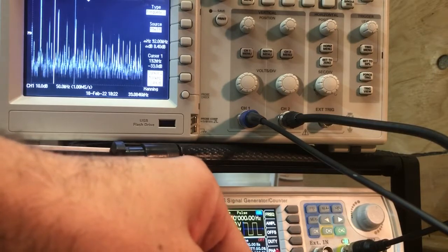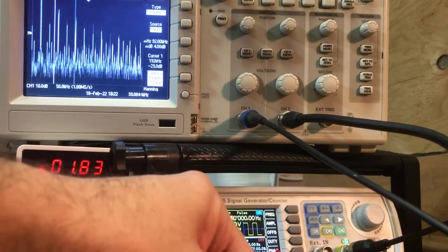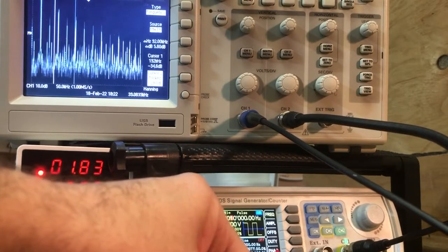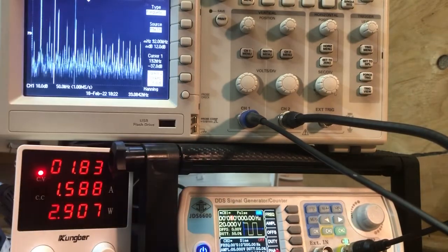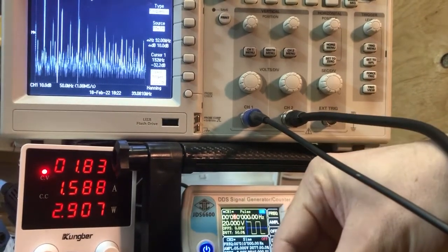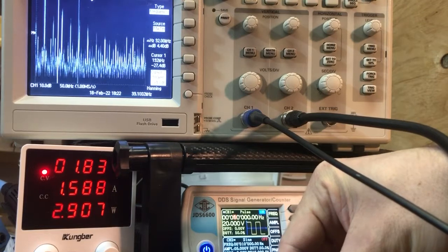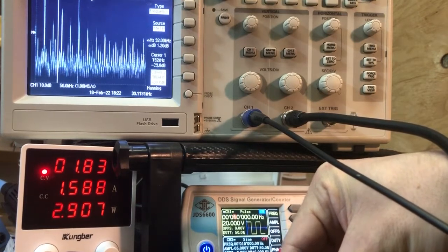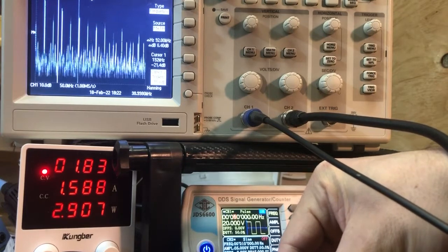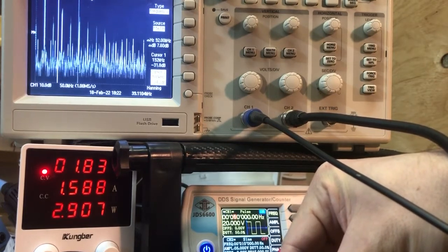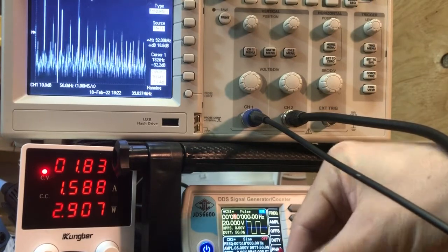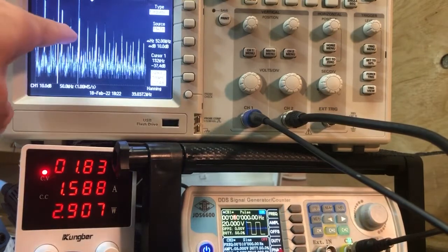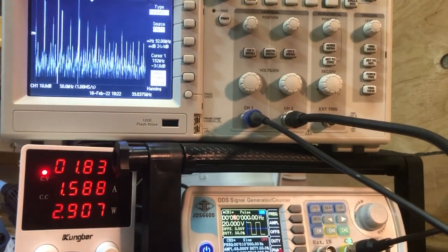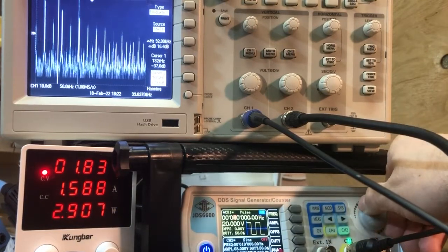Nope, scratch that. It's because high frequency is very directional. As I move my head around, I'm hearing a different sound. Like moving my head back and forth even a quarter of an inch is enough to change the amplitude in my ear. So now we're at 13K. Turn that down. Turn that up. Sure does seem like when I turn up my high voltage to a certain amount, it really evens out the noise in between the amplitudes of my Tesla frequencies.